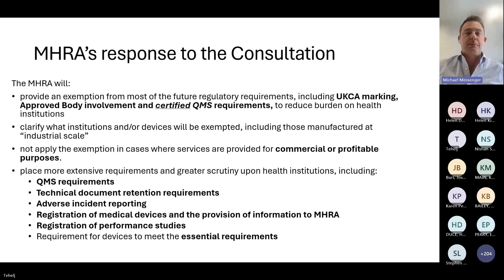They have stated that they will place more extensive requirements and greater scrutiny upon health institutions, including the requirement for a quality management system, technical documentation, retention requirements, adverse incident reporting, registration of devices and the provision of information to the MHRA, registration of some forms of performance studies, and the requirement for devices to meet the essential requirements of the medical device and IVD regulations. Next slide, please.